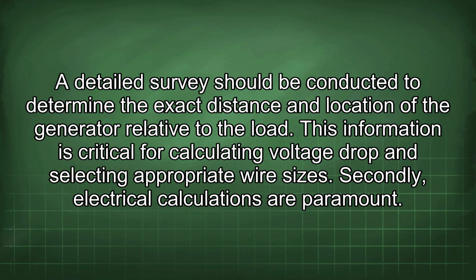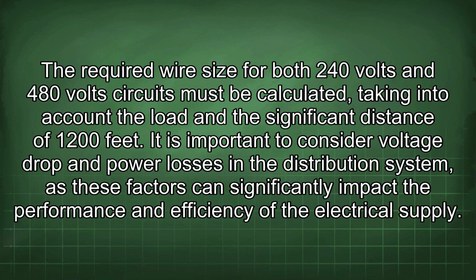Secondly, electrical calculations are paramount. The required wire size for both 240 volts and 480 volt circuits must be calculated, taking into account the load and the significant distance of 1200 feet. It is important to consider voltage drop and power losses in the distribution system, as these factors can significantly impact the performance and efficiency of the electrical supply.